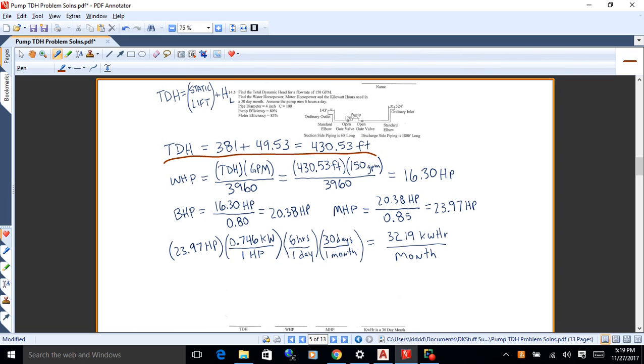From there, you can get horsepower. Horsepower for water horsepower is TDH times GPM over 3960. So you can run those numbers and get 16.3 horsepower that's put to the water. You can then divide the efficiencies out and get to the brake horsepower coming out of the motor. Divide the next efficiency out and we'll get the motor horsepower coming into the motor and that's 23.97. You can then take that number, convert it into kilowatts. It runs six hours a day. We'll assume 30 days in a month. So we can multiply those numbers together. And what we'll get is 3,219 kilowatt hours per month.